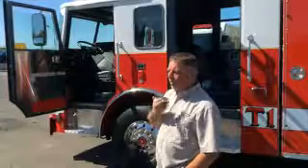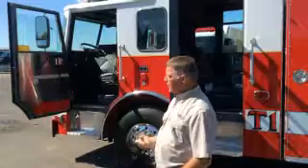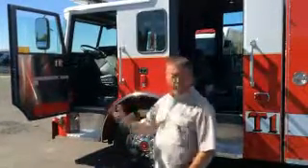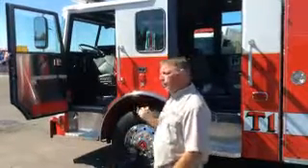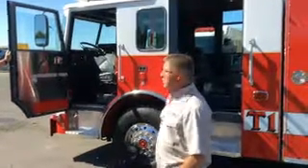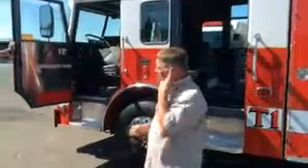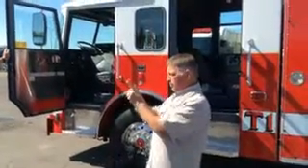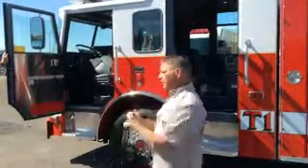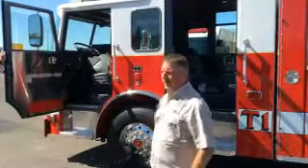That shoreline plug that's plugged in, I tell them not to pull it out, for one thing. Before it kicks that plug out, it shuts power down to that plug so that they don't backfeed and get ghosts in their machine. The other thing is, if they keep pulling it out, they're going to make the firing pin in there weak and it's not going to kick the plug out anymore. So let it do its job, let it kick that plug out. There is another plug in one of those boxes so you can make a tattletale, a little pigtail. Plug it into there, so if it does not work, it separates at the pigtail and doesn't pull the wiring out of the station, which would be bad.